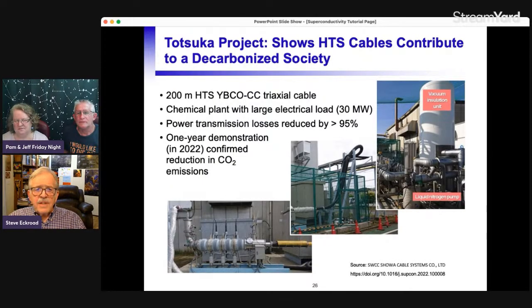There's a project that just finished recently at a private chemical plant in Japan, called the Totsuka Project. Their whole point was to show that HTS cables could contribute to a decarbonized society, and they showed that power transmission losses were reduced by 95% compared to conventional cables. It's a chemical plant that uses a lot of electricity—30 megawatts is a lot, since in your home you only use about 5 kilowatts. It was a 200 meter triaxial cable, a 1-year demonstration, and they confirmed the reduction in CO2 emissions.